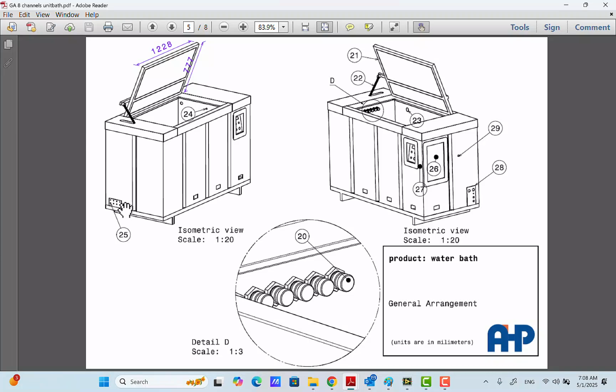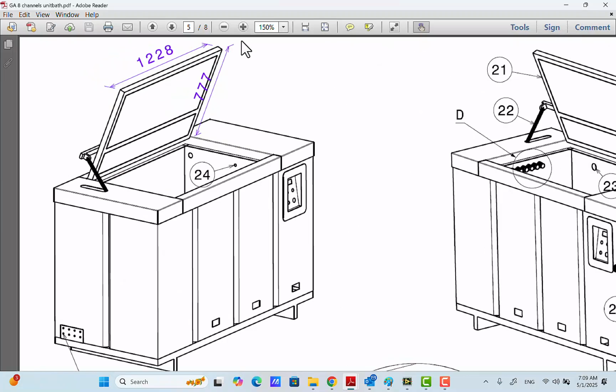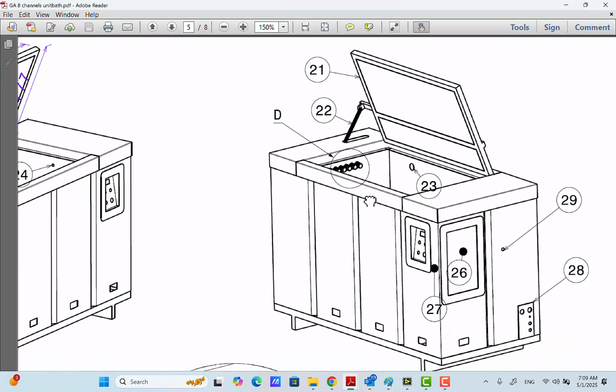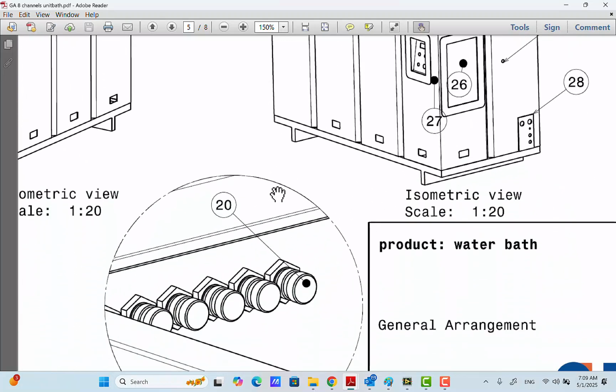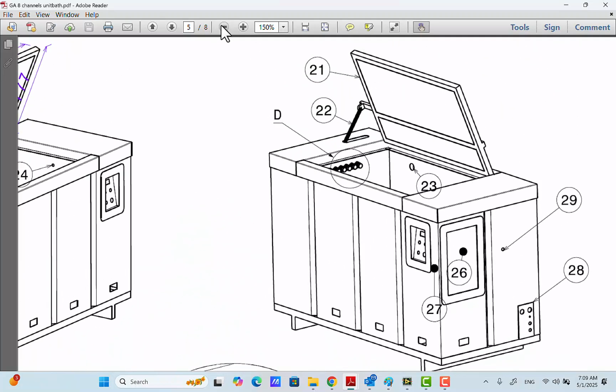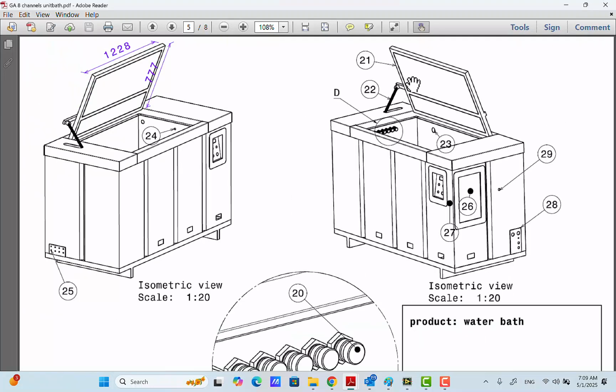The connections are on the left or right side depending on the order and the laboratory plan of the customer. Connections are also 1/4 of an inch BSP or NPT connection. Those are coming into the lines inside the tank with a quick coupling to connect the sample pieces and hang the sample pieces inside the water tank vertically. The lid of the tank is pneumatically opened.